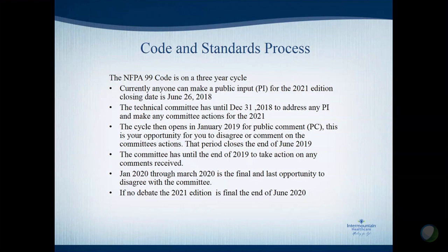But let's say my public input is, instead of requiring you to have one, I require you to have a risk assessment on whether or not you should have an alternative source of breathing air outside the monoplace chamber. So you do your risk assessment, and if you decide that you need to have it, great, have it. If you decide you don't, that's great too. You've done your risk assessment. I think that's probably a better answer than what we've been doing over all these years.